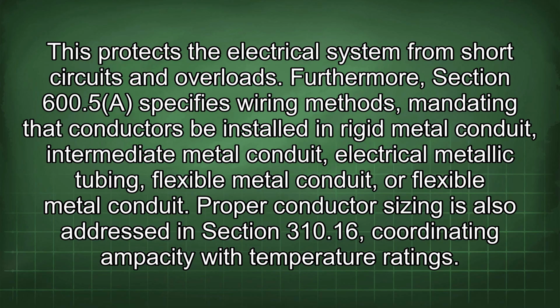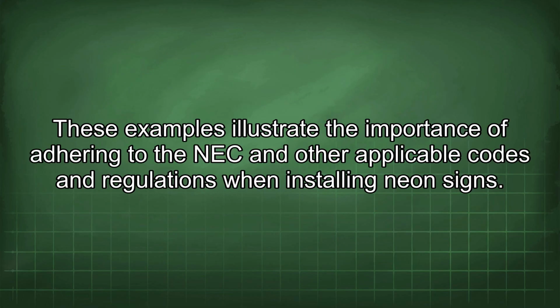Furthermore, Section 600.5 specifies wiring methods, mandating that conductors be installed in rigid metal conduit, intermediate metal conduit, electrical metallic tubing, flexible metal conduit, or a flexible metal conduit. Proper conductor sizing is also addressed in Section 310.16, coordinating ampacity with temperature ratings. These examples illustrate the importance of adhering to the NEC and other applicable codes and regulations when installing neon signs.